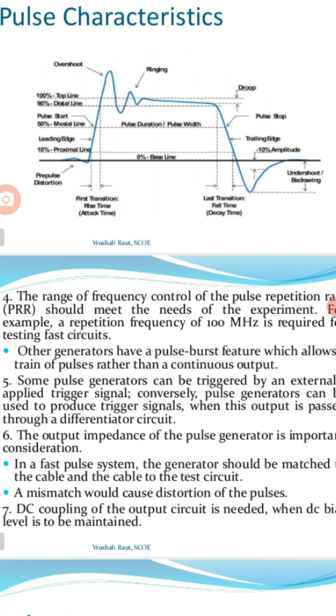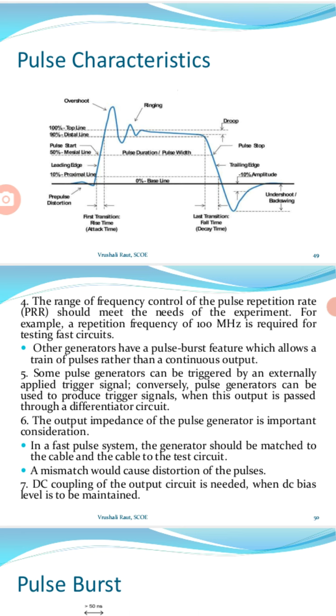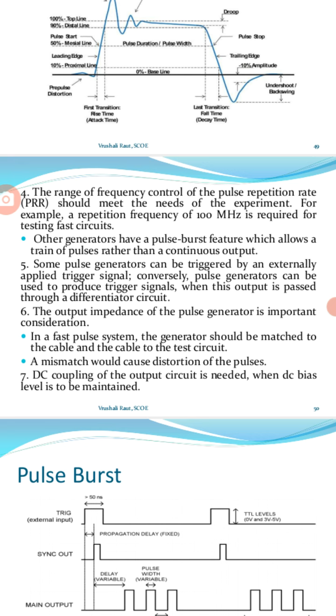The range of frequency control of the pulse repetition rate should meet the needs of the experiment. For example, a repetition frequency of 100 MHz is required for testing fast circuits. Other generators have a pulse burst feature which allows a train of pulses rather than a continuous output. Some pulse generators can be triggered by an externally applied trigger signal. Conversely, pulse generators can be used to produce trigger signals when this output is passed through a differentiator circuit.